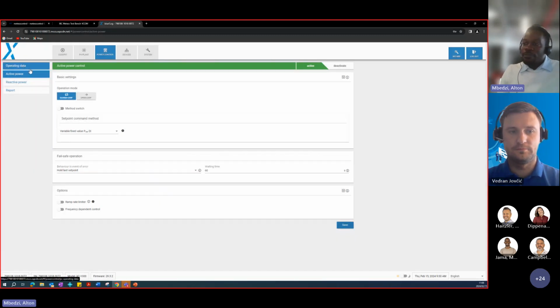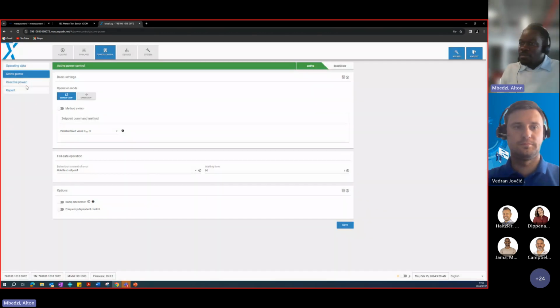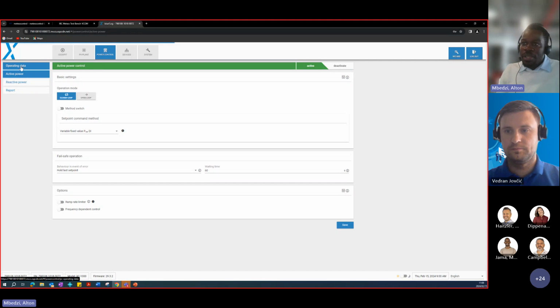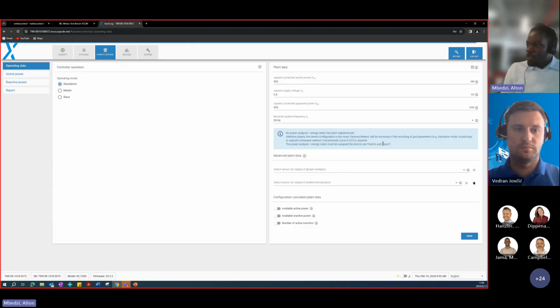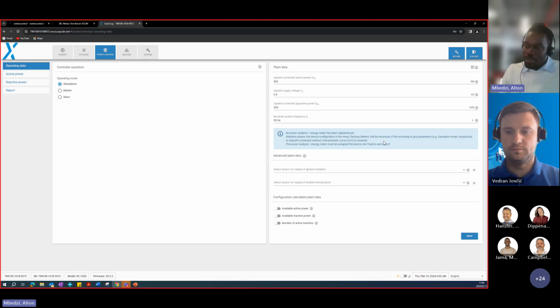But unfortunately, in this case, I don't have a power and energy meter, so it won't allow me. You always have to set your feed-in energy meter. In this case, I don't have one, so it's not going to allow me to do that. Normally, on your operating data, you will see this section where I would select my energy meter to say, I want this energy meter to be my feed-in limit energy meter. But in this case we don't have one, but I hope that helps show how to get your system set up with a generator and also a grid. If you do have a site that you need to commission, please feel free to contact us so we can assist.